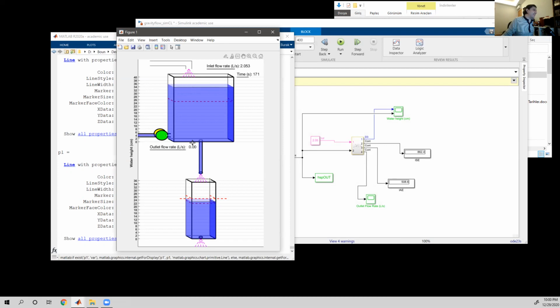there is an excessive control action when there is an error, and due to that excessive control action, this part, the first tank, behaves faster, but the effect is transmitted slower to the second tank. And once you see something is wrong with the second tank, the water level is too high, then it is too late because the first tank has already overflown.